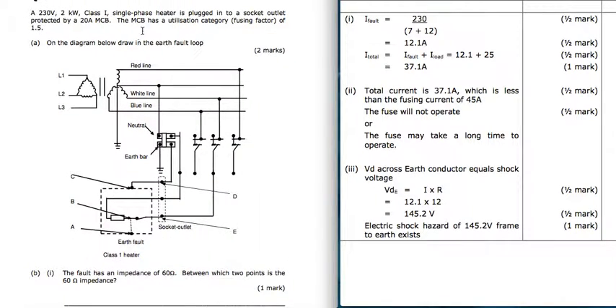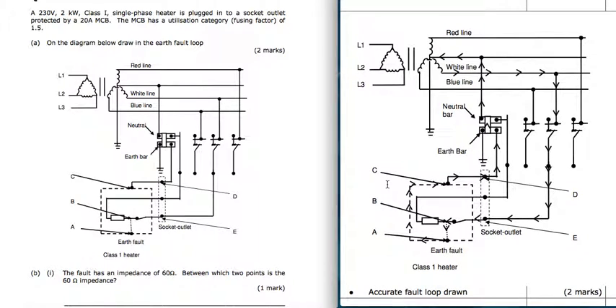So on the diagram below, draw in the earth fault loop. So the earth fault loop would be through that white line, down to the socket, through the fault, through the casing, the earthed casing, through the earth conductor there, back to the MEN link, through the MEN link, back up to the neutral and to the neutral of the transformer, which is shown over here with these arrows.